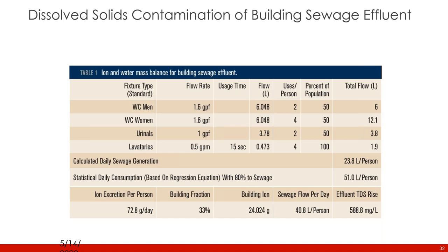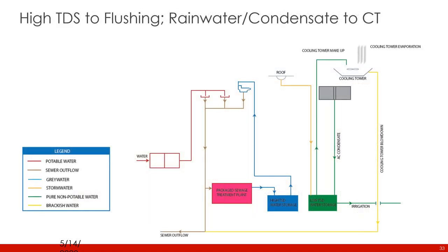That is 589 parts per million. So if the water coming into this building, let's say it's hard water, and it's coming in at 200 parts per million, it's leaving at 789 parts per million total dissolved solids.